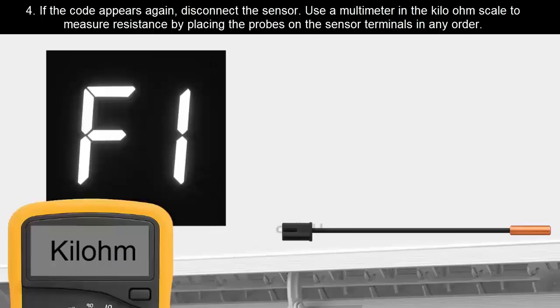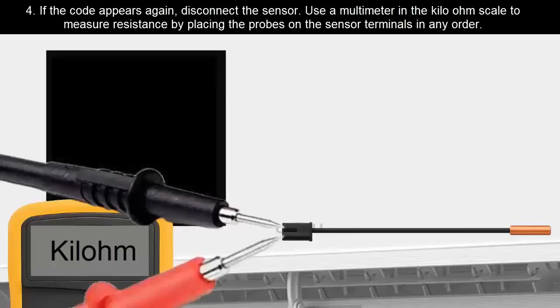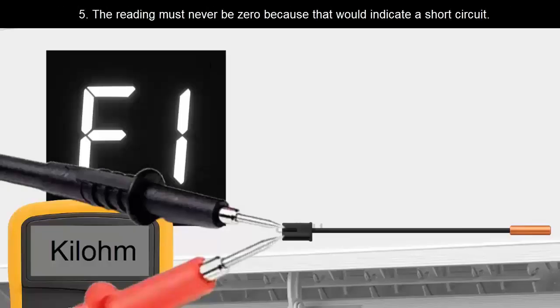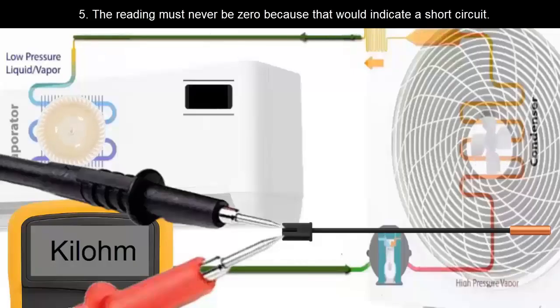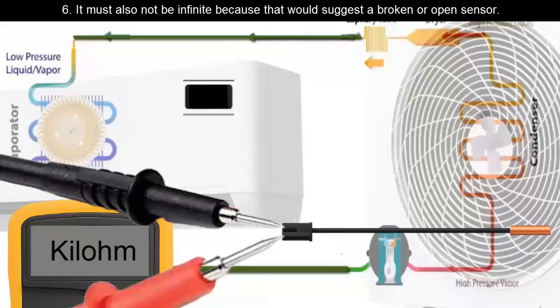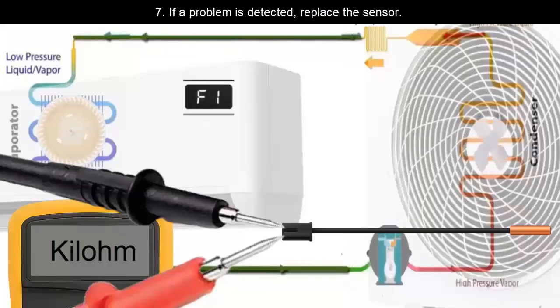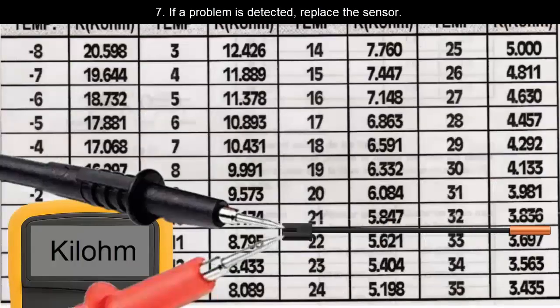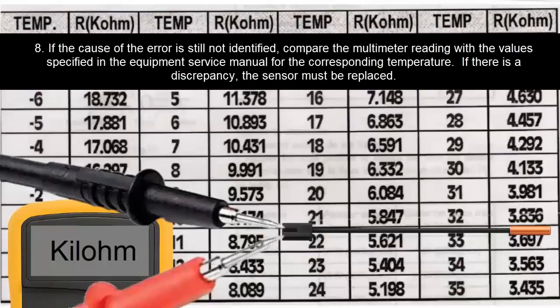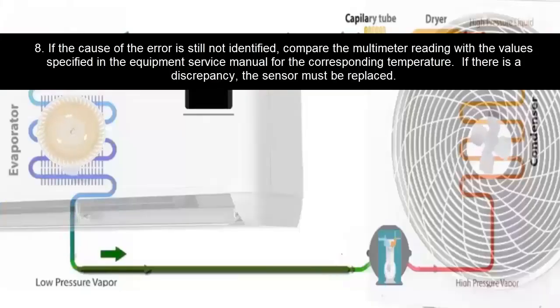4. If the code appears again, disconnect the sensor. Use a multimeter in the kilo-ohm scale to measure resistance by placing the probes on the sensor terminals in any order. 5. The reading must never be 0 because that would indicate a short circuit. 6. It must also not be infinite because that would suggest a broken or open sensor. 7. If a problem is detected, replace the sensor. 8. If the cause of the error is still not identified, compare the multimeter reading with the value specified in the equipment service manual for the corresponding temperature. If there is a discrepancy, the sensor must be replaced.